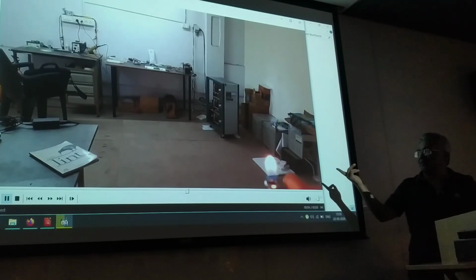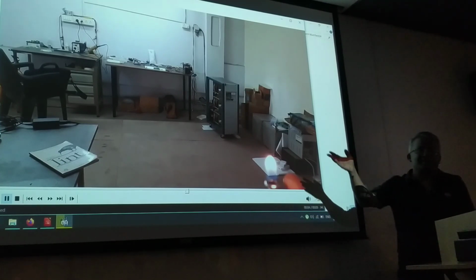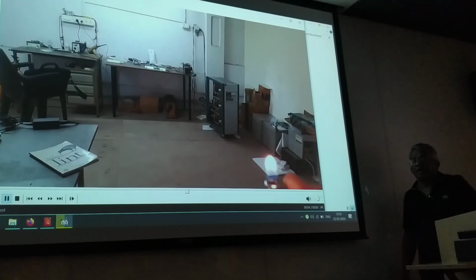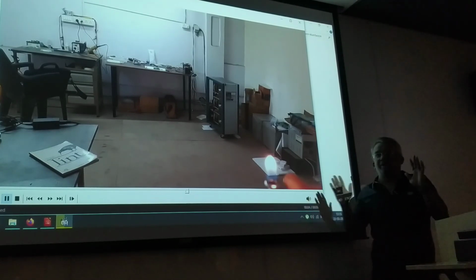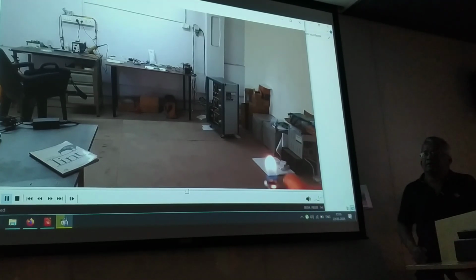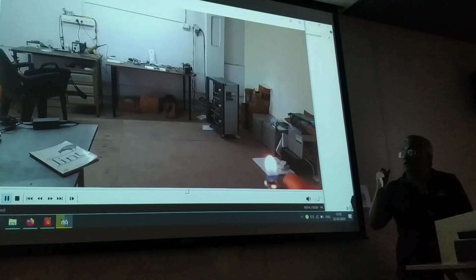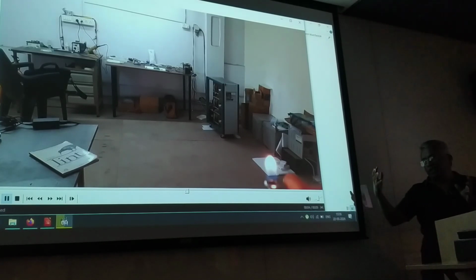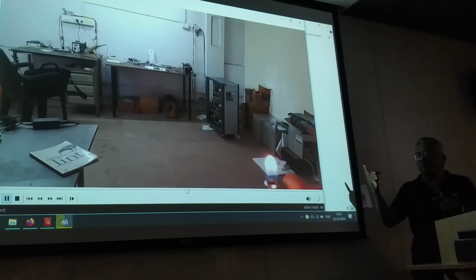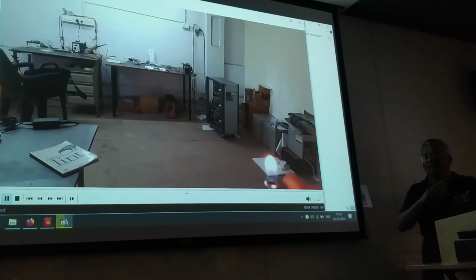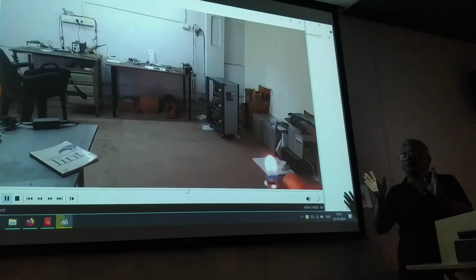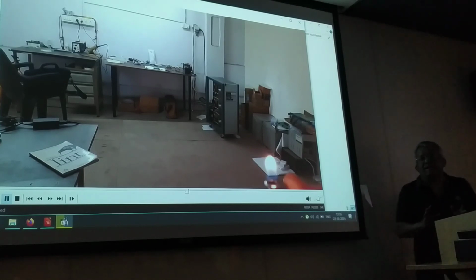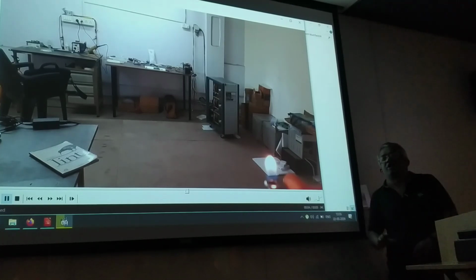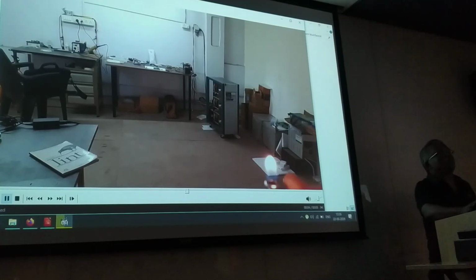So it can detect a candle flame, or actually we were using a lighter. It needs line of sight, like a divergent cone. So you would put multiple of these units. The funny thing is, if this triggers, it will trigger the other one also. So if there are 2-3 of these units, if one triggers, it gets triggered by the other. So you have to mount them so that they don't see each other, and that also helps because the area of coverage gets increased.